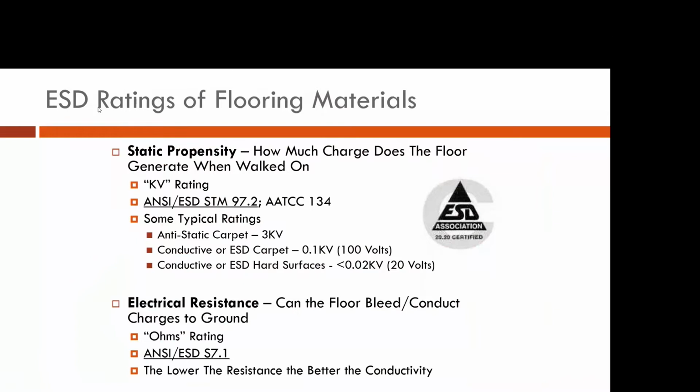Is the charge coming off the body, going to the floor, going to the ground? Is the floor connected to ground properly, and is the operator connected to the floor, which is connected to ground? That's done in two tests: the ANSI ESD S7.1, and then the ANSI ESD STM 97.1.